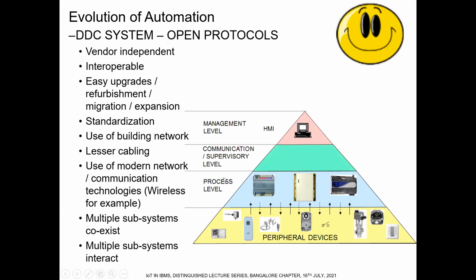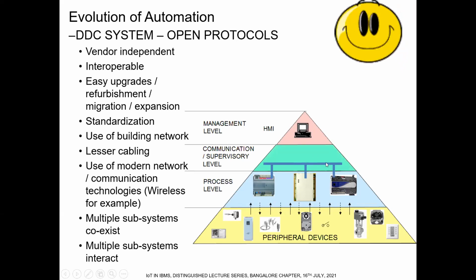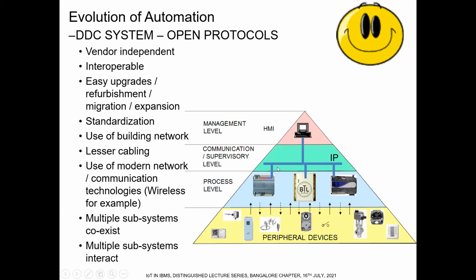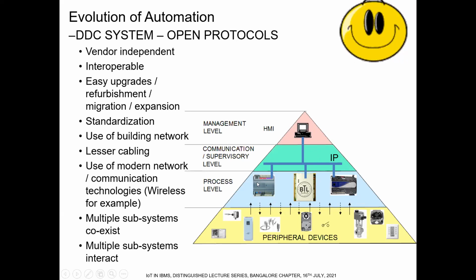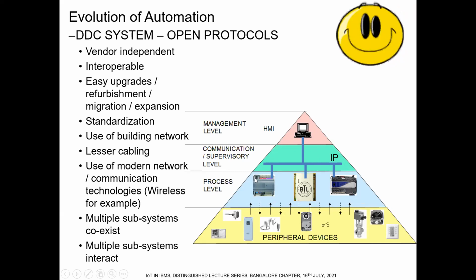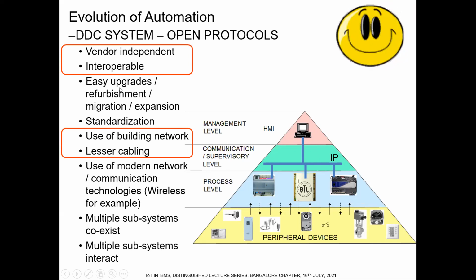This layer disappeared because these controllers were able to sit on the IP network, the building network itself. They took addresses from the IP network, the customer network. And because of the open protocol, an existing system could communicate to a new system from a different vendor, and interoperability started getting better and better. Today, a chiller manufacturer's chiller microprocessor can talk to a BMS vendor. An electrical meter manufacturer can talk to a BMS vendor through the open protocol structure, and they can all sit on the IP network. That is the level of sophistication we have reached. That is the open protocol structure.